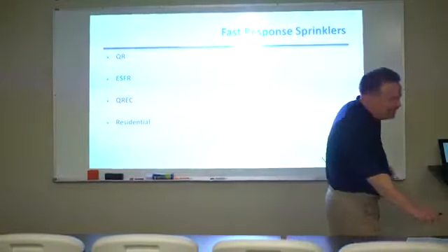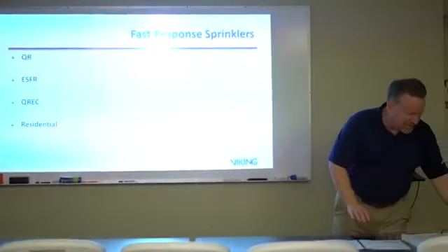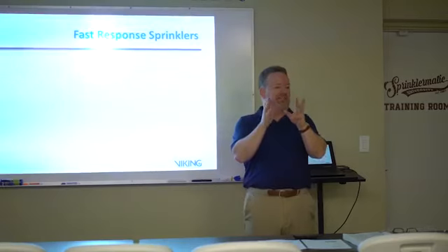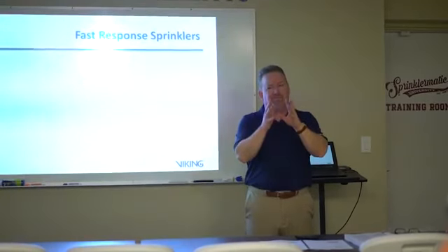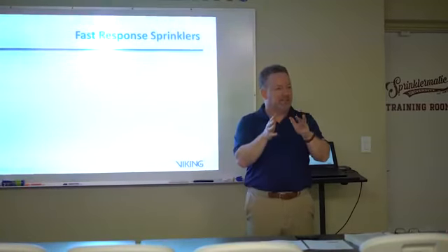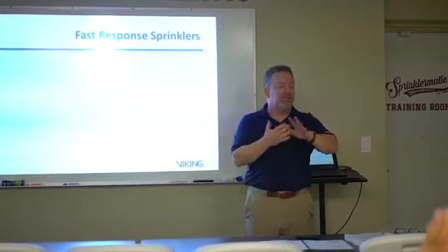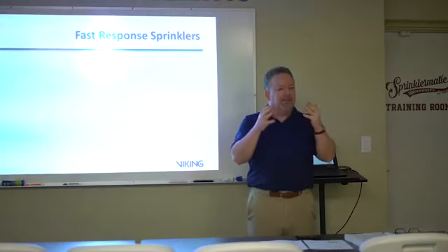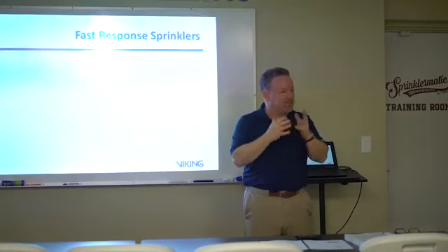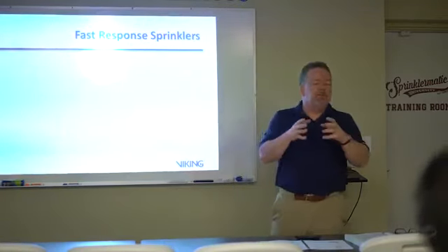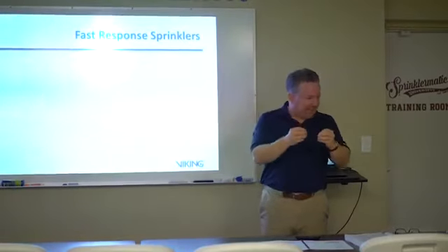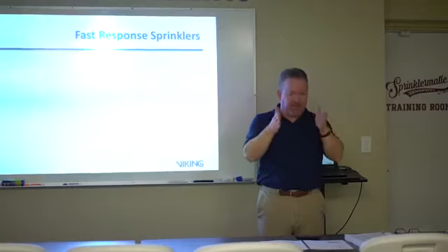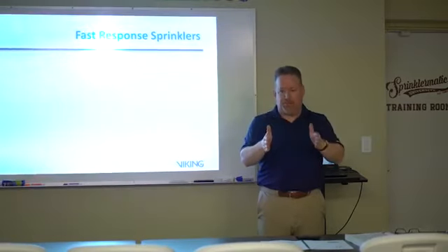Yes, you can be. The terminology gets a little confusing sometimes when you're talking about these. Viking actually has a paper on the difference between quick and fast response. But fast response typically is used to describe the link. It's a fast response link, or a standard response link, and that's based on how quickly it's going to respond to a fire.